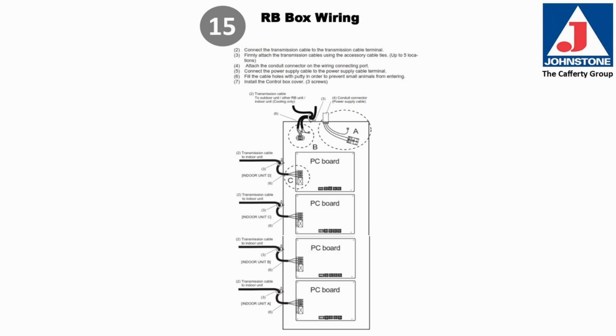Refrigerant branch box wiring. Connect the transmission cable to the transmission cable terminals. Firmly attach the transmission cable using the accessory wire ties. Attach the conduit connector to the wiring connecting port. Connect the power supply cable to the power supply terminal. Fill the cable holes with putty in order to prevent small animals from entering, and install the box cover using the 3 screws we removed.